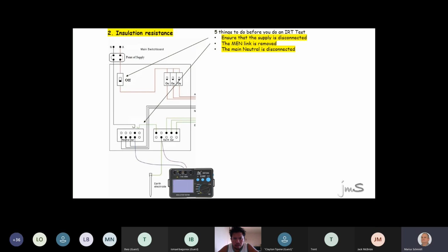Sorry, you guys don't test. You guys test, guys? I hope so. The next thing, unplug all mommy's toasters, kettles, irons, and also the TV and VCR because you don't want to damage them. And if one of them has got a fault and you do a test, your instrument will give you a fault reading. So then you say there's something wrong with that plug circuit. Meantime, it's mommy's dodgy toaster.